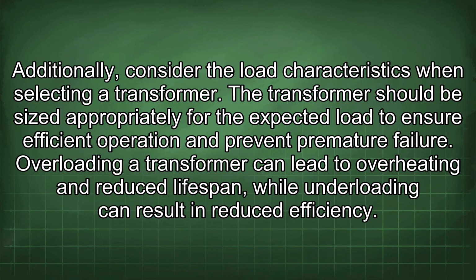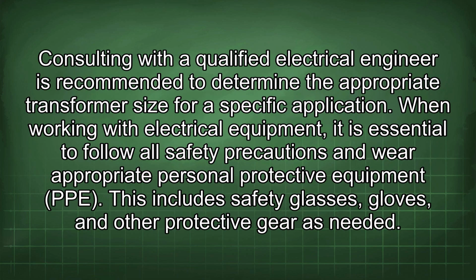Additionally, consider the load characteristics when selecting a transformer. The transformer should be sized appropriately for the expected load to ensure efficient operation and prevent premature failure. Overloading a transformer can lead to overheating and reduced lifespan, while underloading can result in reduced efficiency. Consulting with a qualified electrical engineer is recommended to determine the appropriate transformer size for a specific application.